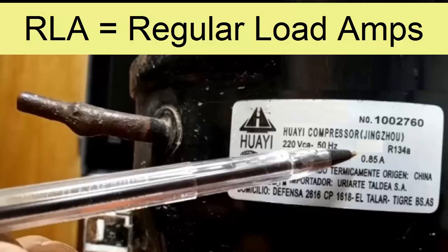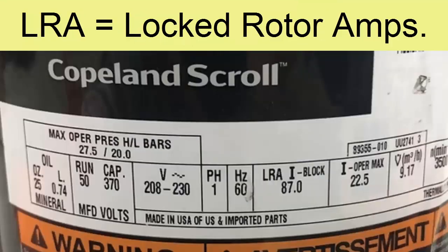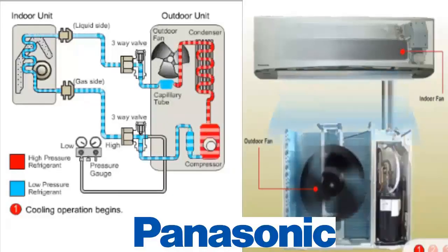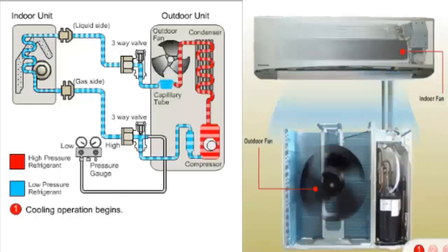When the equipment is running, the parameter to compare is the RLA, while immediately at the moment of the equipment's startup, the comparison parameter should be the LRA. When the measured value exceeds the current consumption parameters on the plate, we should consider the following recommendations.